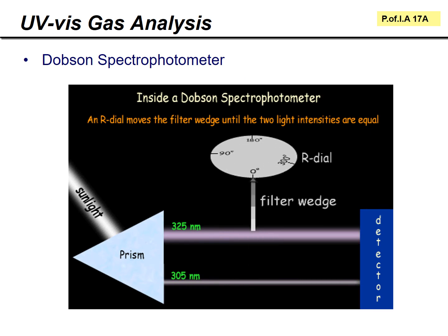Because the signals are quite different and the dynamic range in UV-Vis is limited to, at most, really an order of magnitude. If you go from absorption of 0.1 through to 1, you've covered the whole range of fraction of light absorbed. Absorption values of less than 0.1, you only have a few percent of light absorbed, and greater than 1, you only have a few percent being transmitted. So that's pretty much the dynamic range.